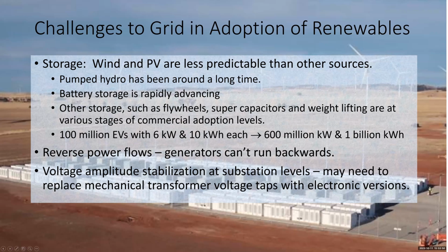So we have to look for voltage amplitude stabilization, but energy management is also coming down the line like gangbusters. Energy management is really going to try to level out the loads, period. They've been doing that with water heaters, swimming pool pumps, and air conditioners for 40 years - connecting them up so they can shut off your pool pump for 15 minutes in the afternoon to help reduce demand. It's no big deal - the pool doesn't care, and the air conditioner or water heater, for the most part, doesn't care either.